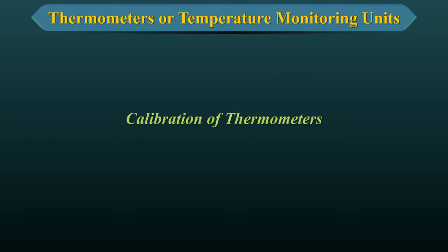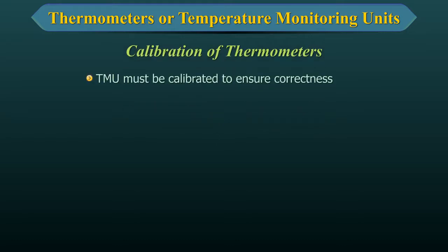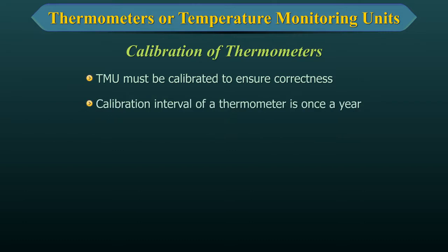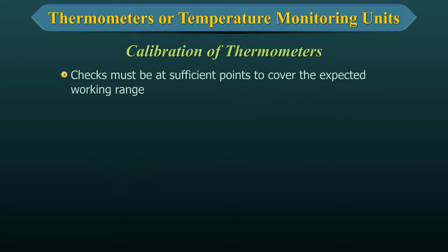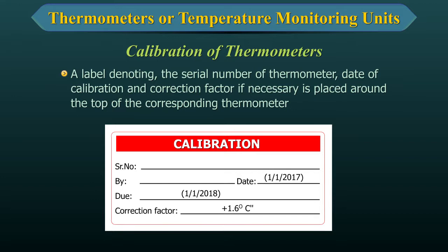Calibration of Thermometers. The TMU must be calibrated to ensure correctness. The calibration interval of a thermometer is once a year. The thermometer must be checked against a calibrated reference, and the checks must be at sufficient points to cover the expected working range. A label denoting the serial number of the thermometer, date of calibration, and correction factor if necessary is placed around the top of the corresponding thermometer.